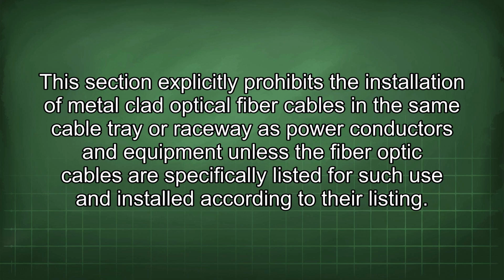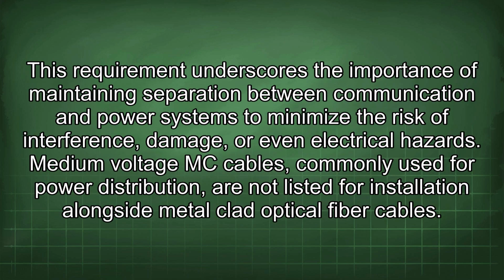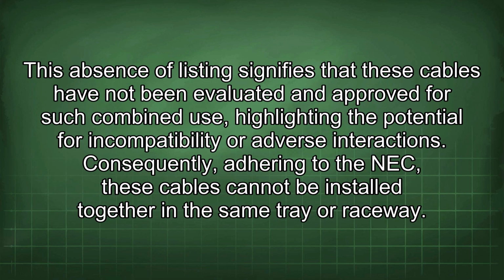This section explicitly prohibits the installation of metal-clad optical fiber cables in the same cable tray or raceway as power conductors and equipment unless the fiber optic cables are specifically listed for such use and installed according to their listing. This requirement underscores the importance of maintaining separation between communication and power systems to minimize the risk of interference, damage, or even electrical hazards. Medium-voltage MC cables, commonly used for power distribution, are not listed for installation alongside metal-clad optical fiber cables. This absence of listing signifies that these cables have not been evaluated and approved for such combined use, highlighting the potential for incompatibility or adverse interactions. Consequently, adhering to the NEC, these cables cannot be installed together in the same tray or raceway.